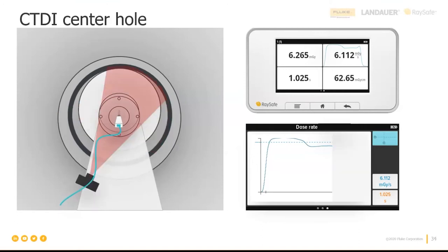Yes. So the CT sensor is in the center of the phantom, and when the tube is below the couch, the radiation passes through more matter, because it goes through the couch and the phantom. And that's what we see in the waveform. And here we are outside of the couch again, and the waveform goes up at the end. Great.